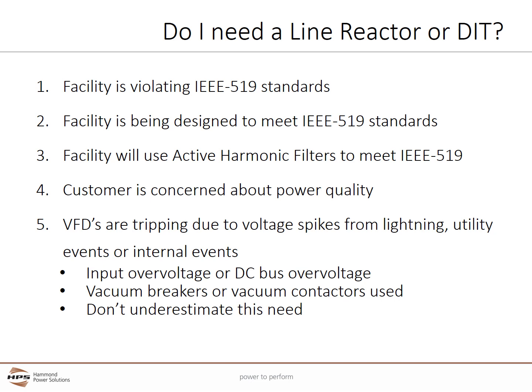Number 4, if a customer expresses concern about power quality, then they really should have line reactors or DITs on their VFDs. This is a broad statement, but generally facilities such as hospitals, data centers, research centers, and industrial operations, which must have high degrees of uptime, are all concerned about power quality. And finally, number 5, VFDs can start to experience tripping events that are often the result of voltage spikes. This will often show up as an input or DC bus overvoltage fault. While people often associate line reactors with reducing current harmonics, another very important benefit is their ability to mitigate a variety of voltage disturbances, which can cause a drive to trip. This will often manifest itself as an input overvoltage or DC bus overvoltage.